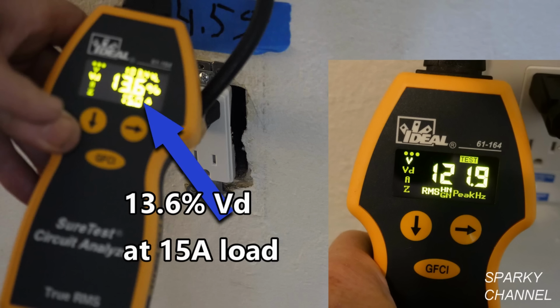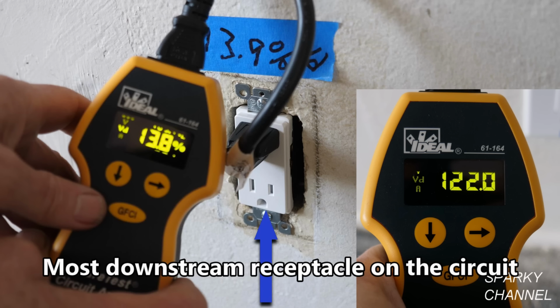The sixth receptacle now reads 13.6% voltage drop at 15 amp load, down from 14.5% with the no load voltage at 121.9 volts AC. And the seventh and most downstream receptacle on the circuit now reads 13.8% voltage drop with the 15 amp load, down from 13.9% with the no load voltage still at 122 volts AC. So the no load volts AC really didn't drop as we were progressing along the circuit.